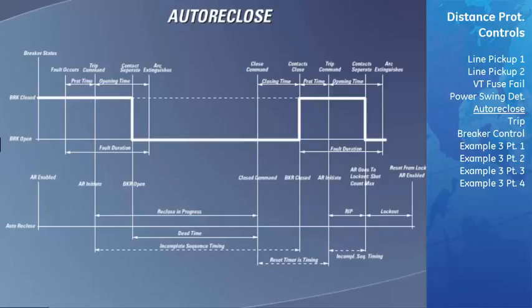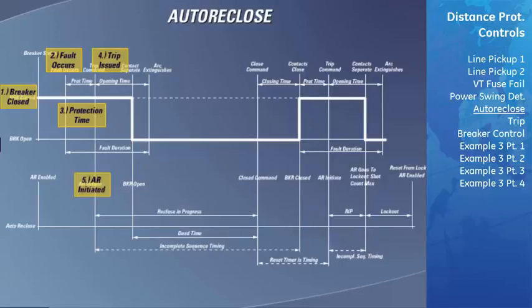The sequence of the three-pole recloser operates as follows for a single-shot reclosing. On our example power system, the breaker is closed, the system is running as normal, and the auto recloser is enabled. At some point, a fault occurs on the protected line. This fault is then sensed by the D60. The D60 will then issue the trip command. At the same time the trip command is signaled, the auto recloser gets initiated, which starts the reclose in progress status. There will now be a brief delay until the breaker has completely opened.